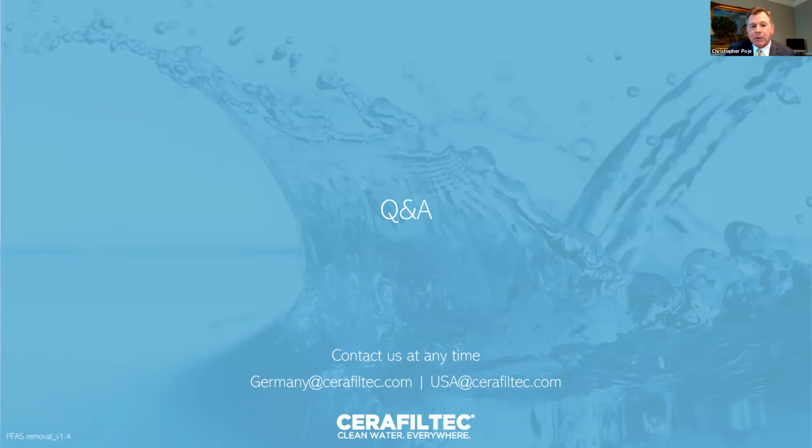So the PFAS by its very nature is soluble. So anything that were to break through the carbon actually goes right through the membranes too. So there's not a case where the PFAS accumulates in the membranes per se, but each time the entire system is backwashed and that small amount of waste goes out. And again, it's a very efficient backwash process, not at all like a conventional plant or polymeric membranes. Very efficient backwash process. That small stream of waste, including the powdered activated carbon, goes out for waste treatment.